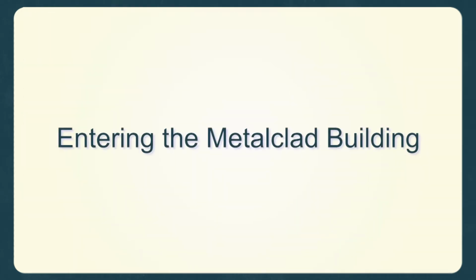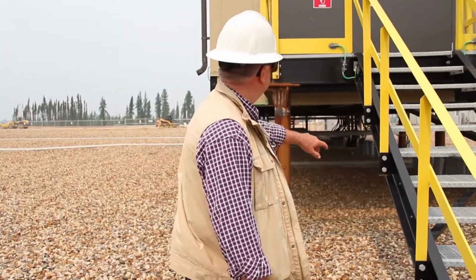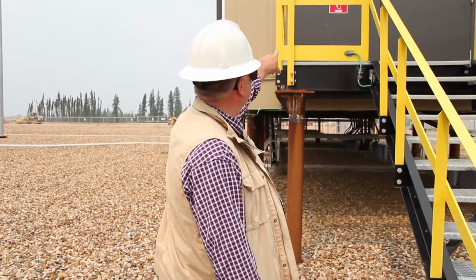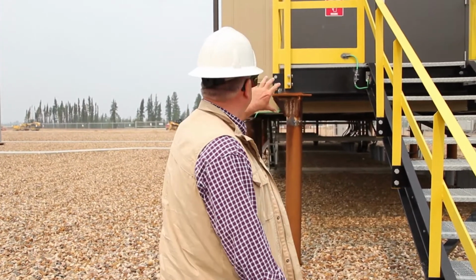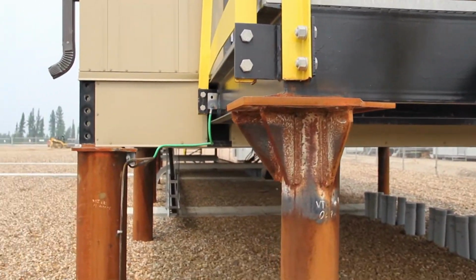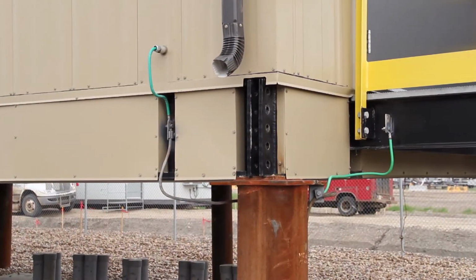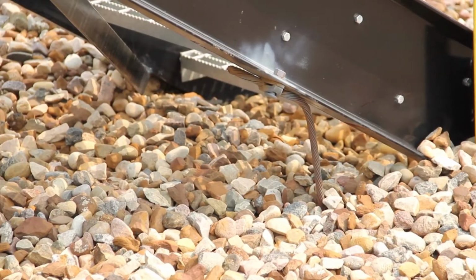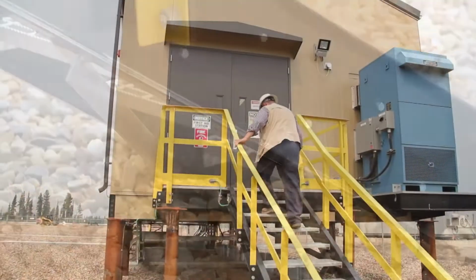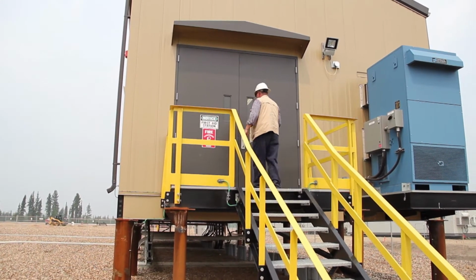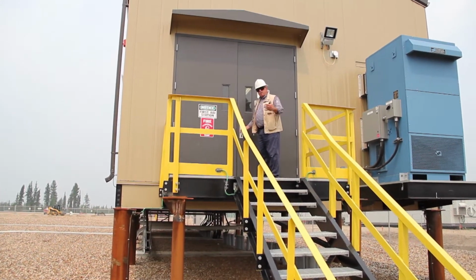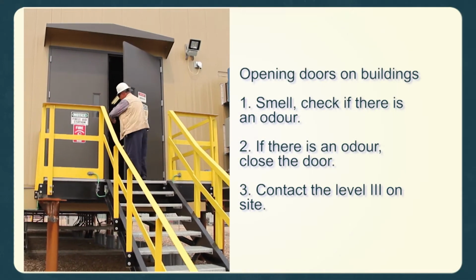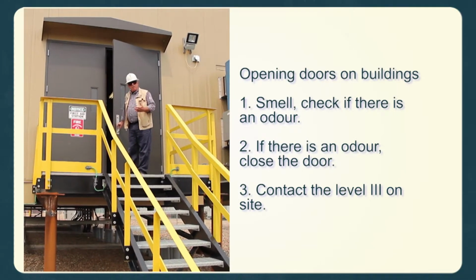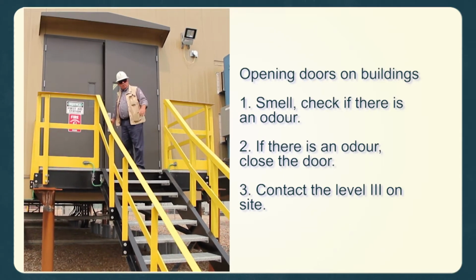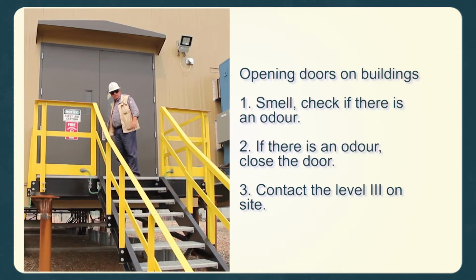Entering the metal-clad building. As you come up to any building on site, the stairs, the platform, the railing, everything has to be bonded into the building. As you come up to the door on the building, there's a couple of things I want you to be aware of. If you open the building and you get a smell like a burnt motor smell, close the door, get a hold of your level 3. Something's gone wrong inside the building.